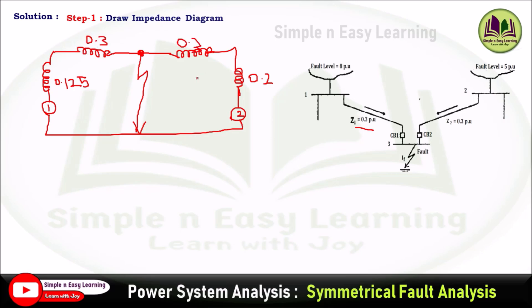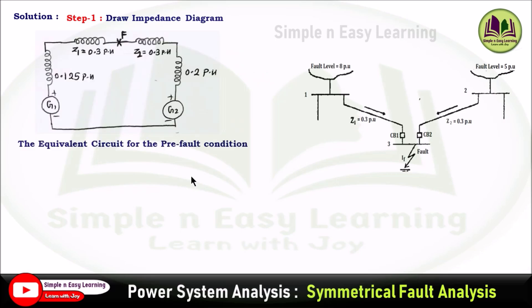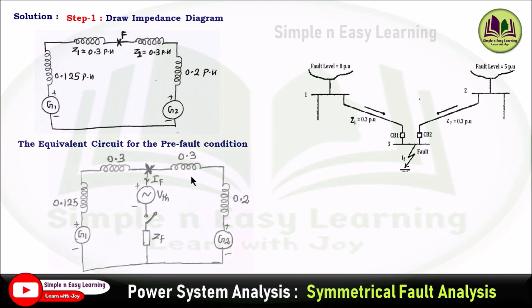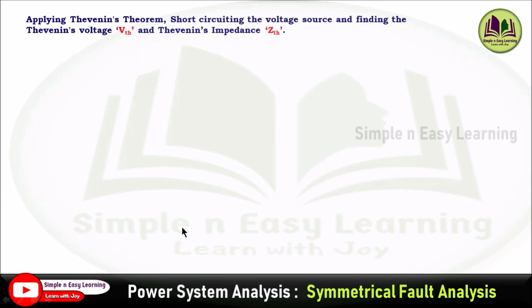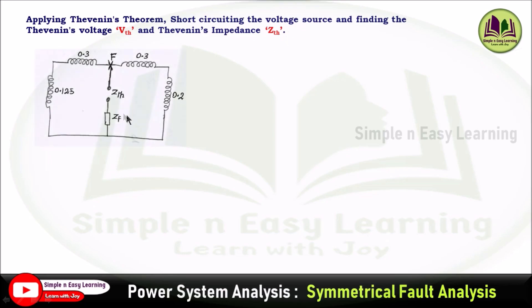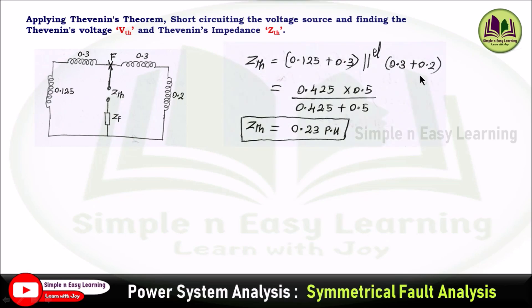This is the complete impedance diagram. The equivalent circuit for the pre-fault condition is represented including the Thevenin voltage source and fault impedance. Applying Thevenin's theorem, we short-circuit the voltage sources and find the Thevenin impedance Z_Thevenin from the fault point. Looking from bus 3, on the left-hand side 0.125 and 0.3 are in series; on the right-hand side 0.3 and 0.2 are in series. Both results are then in parallel with each other.